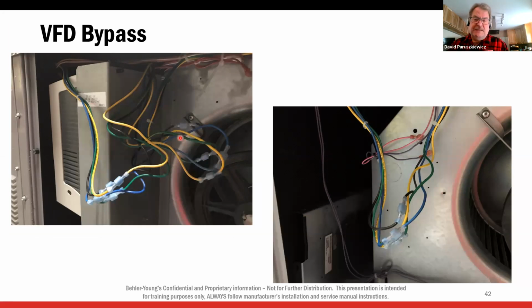So I can simply bypass that drive if I need to. Now, if you do this, remember there's no contactors. So that blower is going to run nonstop 7 days a week until you get back there with the VFD. But in a pinch, I can simply bypass the VFD to get the motor running.